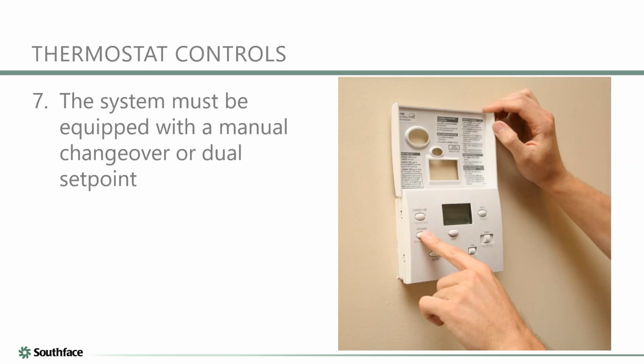All right, the next one on the list here is thermostatic controls. You're going to see there's a number of things on this list that are basically tied to what type of thermostat, or what type of function, your thermostats have. This one is pretty basic, and it either needs to be dual set point or manual changeover. That means that essentially a person has to come and switch between the heating and cooling mode, or that there is a degree of deadband, if you want to call it, between the temperature you're heating up to and the temperature you are cooling down to. So, most standard programmable thermostats would do this, or a manual changeover that you physically have to switch between cooling mode and heating mode.